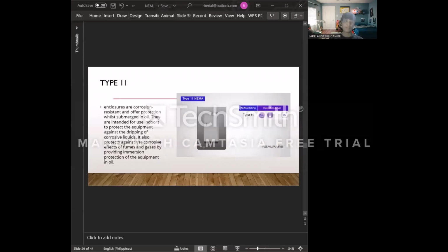Next type is the type 11 rather. Type 11 NEMA rated enclosure. So, these enclosures are corrosion resistant and offer protection while submerged in oil. So, they are intended for use indoors only to protect the equipment against dripping of corrosive liquids. So, it also protects against the corrosive effects of fumes and gases by providing immersion protection of the equipment in oil. So, yun, no? Ginagamit na siya sa indoor and it can be submerged in oil and water resistant din siya.